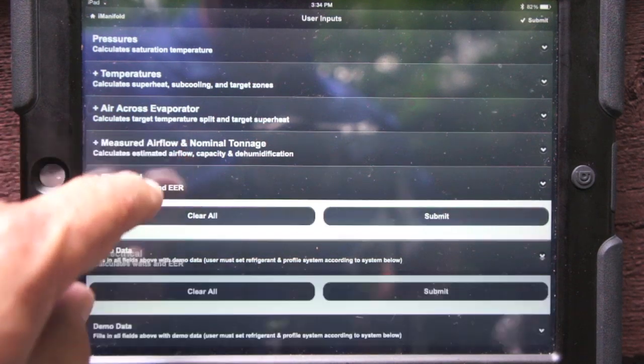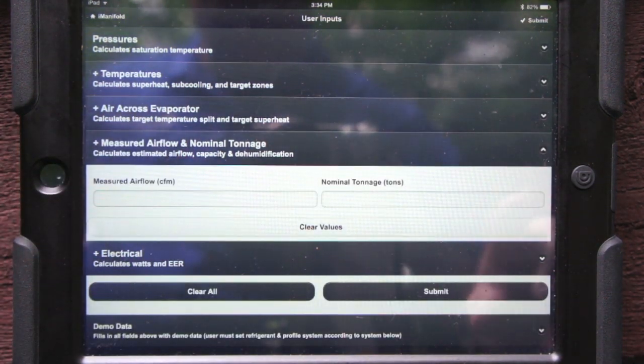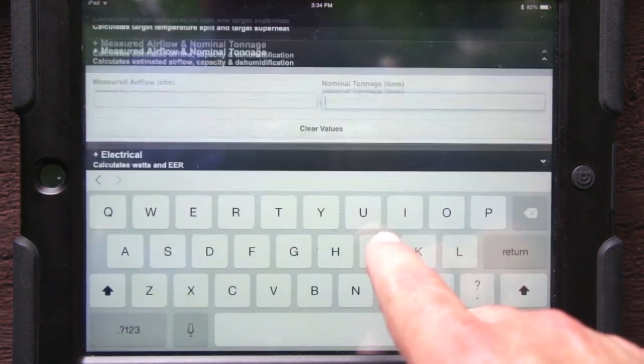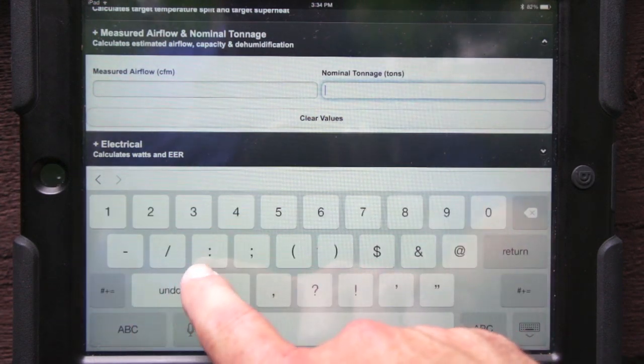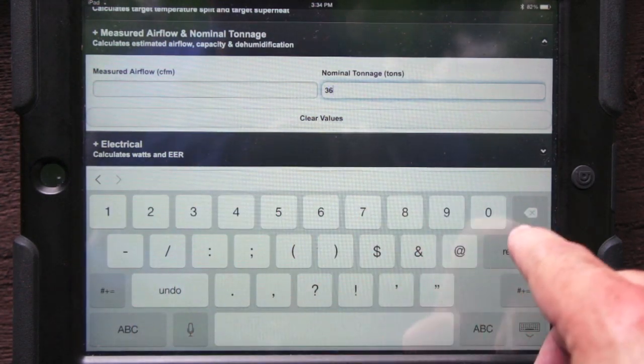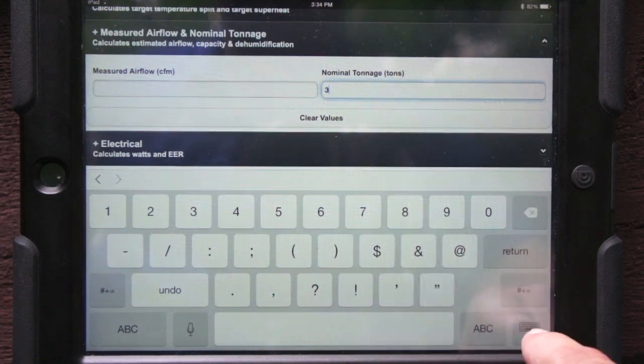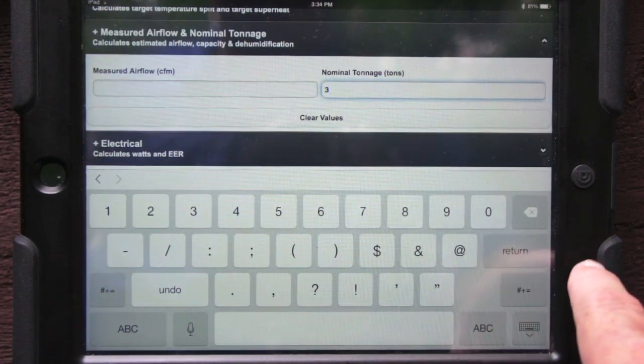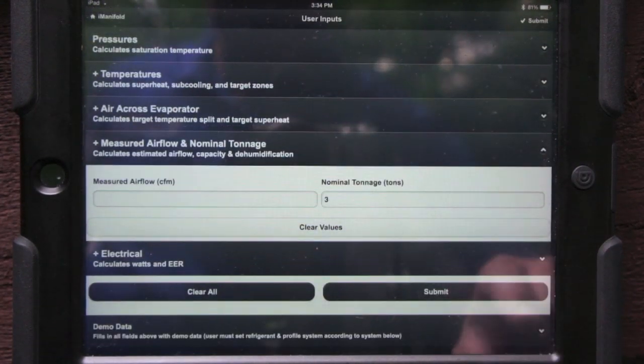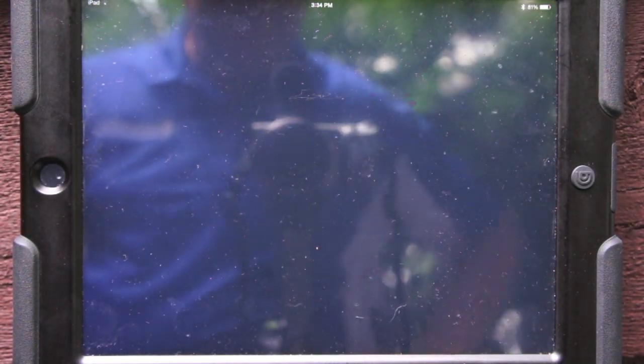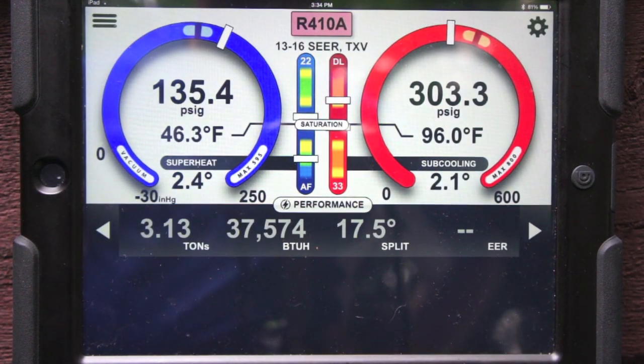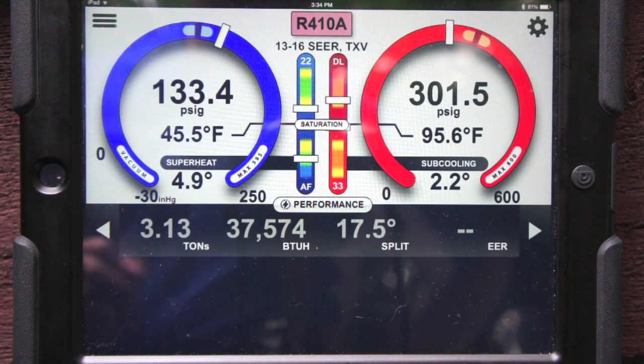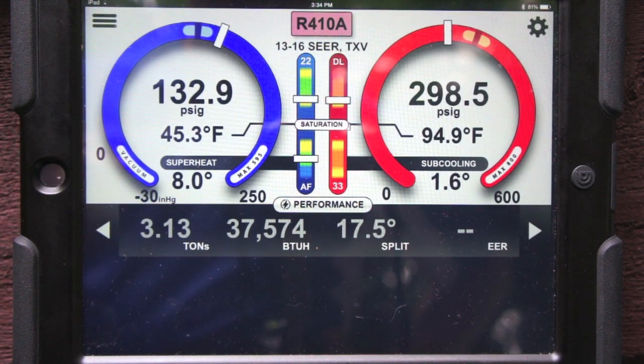If we go into the airflow and tonnage, I'm going to show you a really neat feature here. We're just going to put in the tonnage. This is a 3-ton unit, so I'm going to put 36 in here. Oops, sorry, just 3. It's 36,000 BTUs, 3 tons nominal. Hit submit. When I hit submit here, now we're going to start calculating performance. Now I want you to notice something. We're calculating BTUs in real time now without inputting airflow.